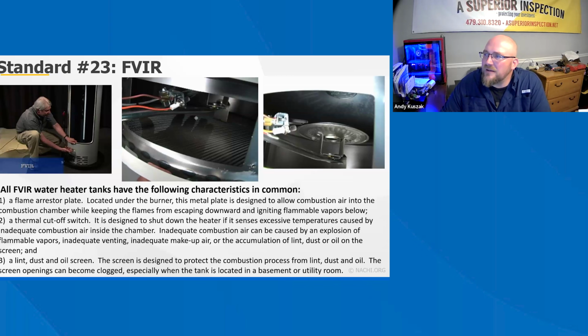FVIR systems on Bradford White Defender water tank during normal operation. Air for combustion is drawn into the water heater through the openings in the jacket. This air travels down and around the combustion chamber and enters through the holes in the very bottom of the corrosion-resistant combustion chamber. The air then travels up through the oriented flame arrestor plate louvers, where the velocity of the air is increased and its direction altered. The air then mixes in a normal manner with the supplied gas and is efficiently combusted, producing very low nitrogen oxide emissions. In the case where trace amounts of flammable vapors are present in the air flowing into the chamber, the vapors are harmlessly ignited by the burner pilot flame.